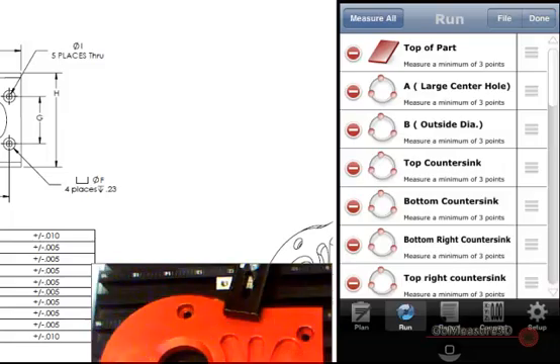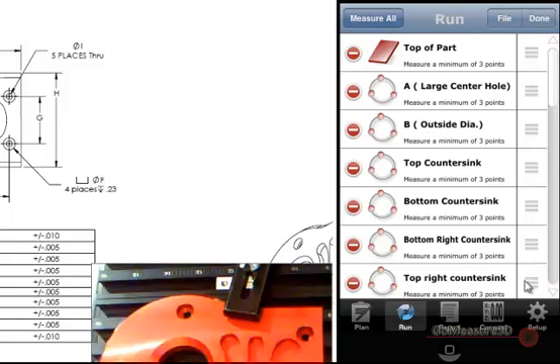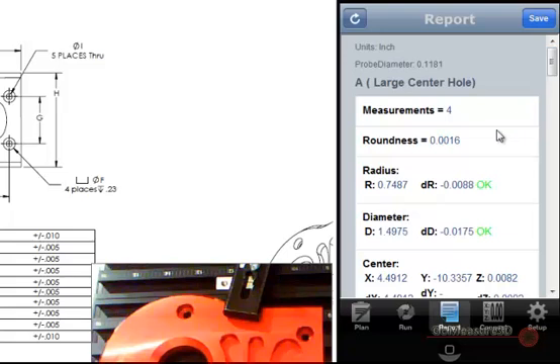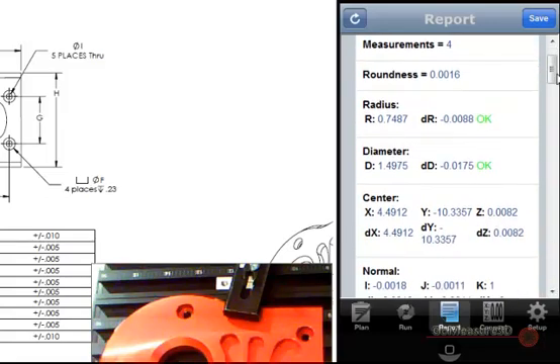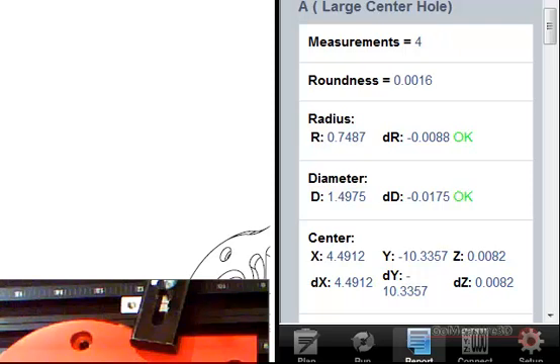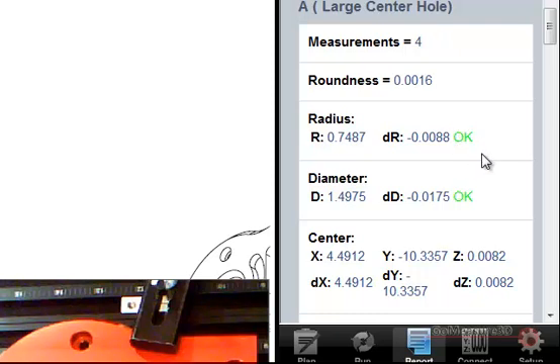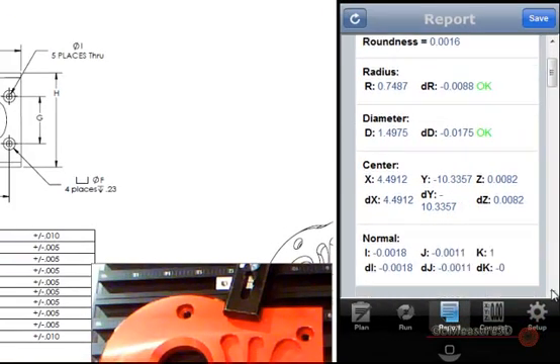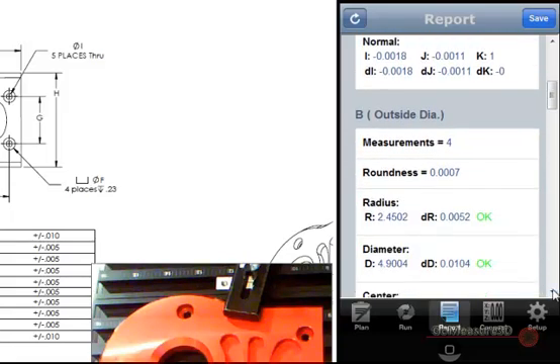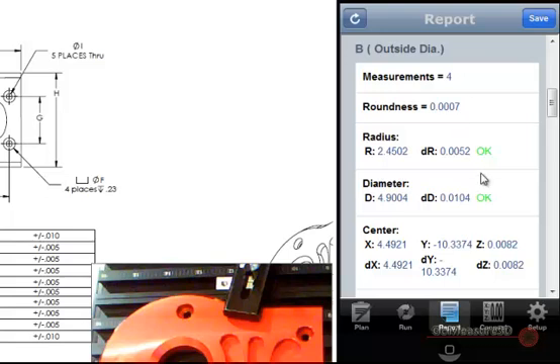This concludes the measurements necessary. Let's take a look at the results — we'll go over to our report plan and scroll up to the top. Here are the results of our measurement process. We get data for measurement A, which is the roundness call-out, showing the radius we measured, the nominal, and the deviation from the nominal, as well as the diameter and its deviation, and some XYZ information. We also notice there is a green OK — that's a go/no-go gauge telling us the part is within the tolerance we set up. If it were not, it would be colored red. Outside diameter, same process — giving us a green for OK.